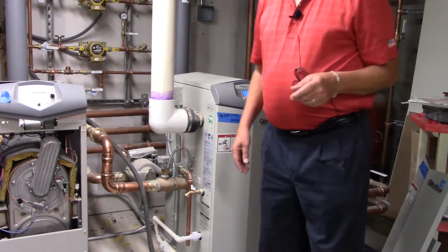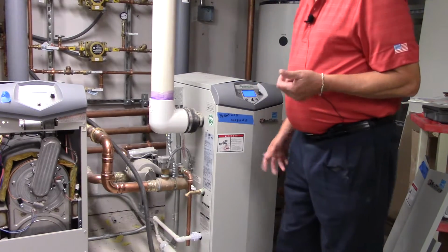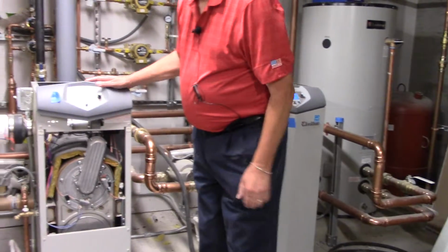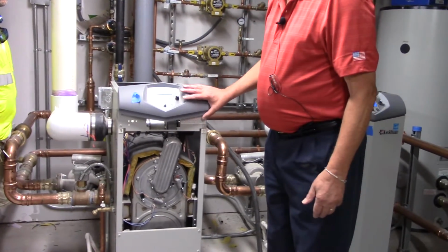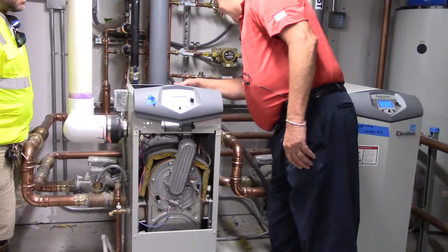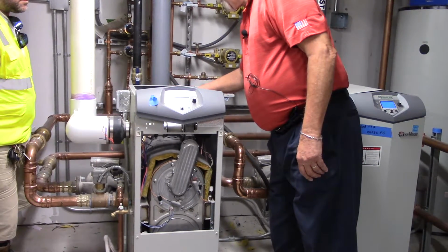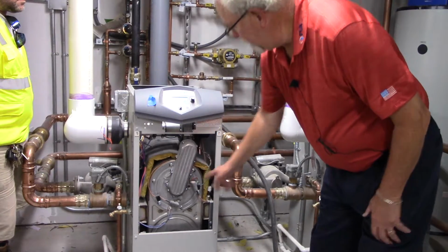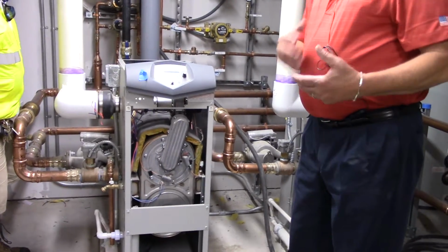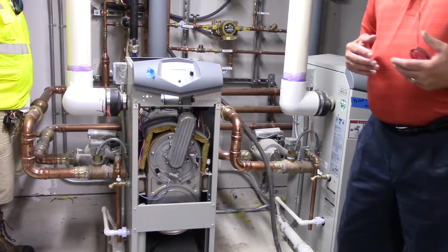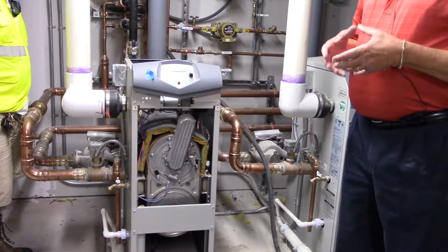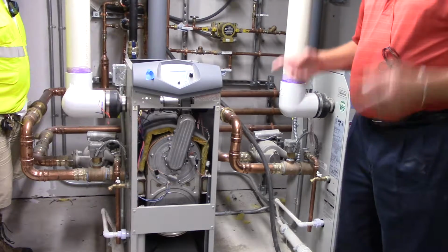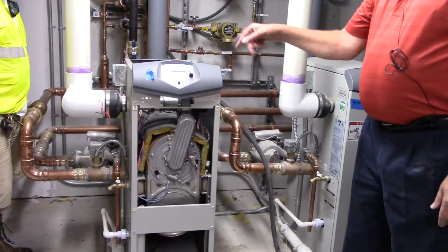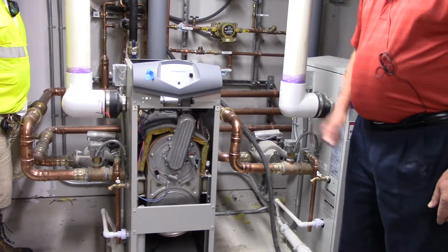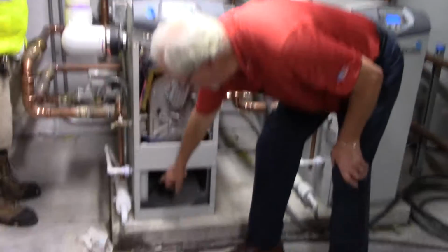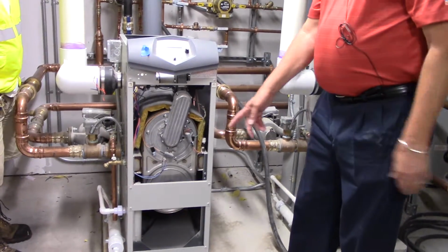These units need to be cleaned annually. They are a water tube unit, so to clean them involves taking this bezel off, breaking the connection at the fan with the gas valve and the air, unbolting this and taking the whole assembly right off. There are kits available that Lochinvar packages, which have a plastic brush on a mandrel inside of it. You put those in your drill, and you basically clean around the coils, flush it out. You disconnect your condensate drain and let it all flush out into your drain out here.